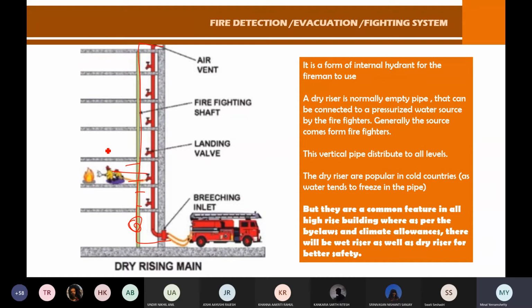The problem with the dry riser is that it cannot go all the way up to the 160th floor. If there's a fire, the internal hydrant is the only thing there, because you won't have that kind of pump which can push water that high. Imagine a fire at the top floor of Burj Khalifa - how can a generator from fire trucks push water all the way up? This is a dry riser, not that small water pipe - this is huge, 6 inches or even more, because of the high rise. So these are all things you'll have to take care of when studying fire safety in your own case studies.